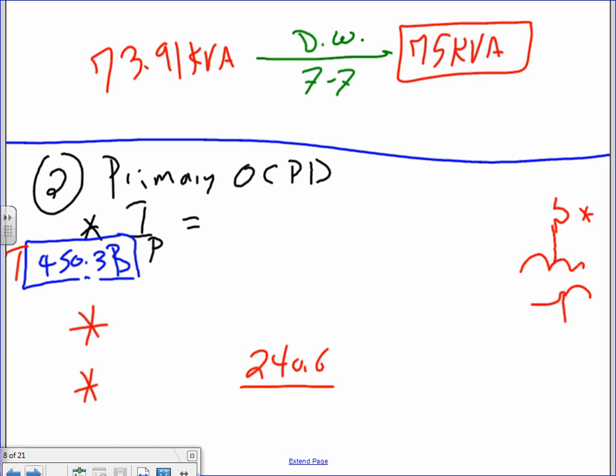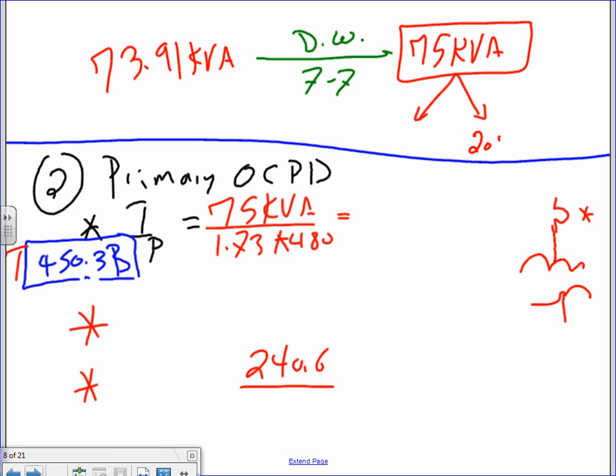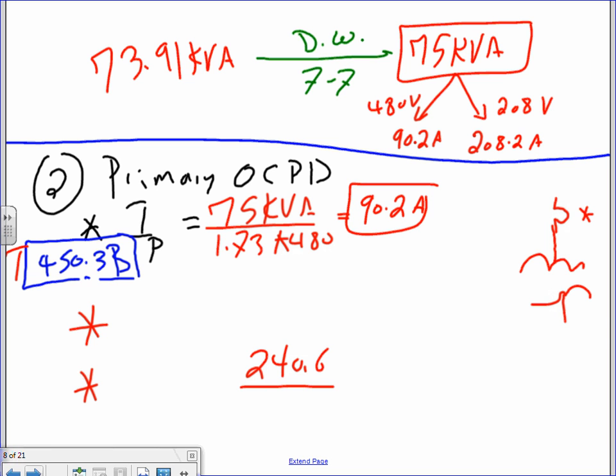Okay, now after this, Adam, straightforward. We found the size, 75 kVA, drop it in Revit, and then I need somebody to help me with the calculation. kVA, divide this by 1.73 times 480. And by the way, this is also coming from the sheet. Derek, why don't you give me this from the sheet right away? The full load amp for the two of them, because it's already there. 75 kVA, at 208 volt, and at 480 volt, 90.2 amps. That's directly from the sheet, guys. When you do the math here, you should come up with 90.2 amps. Or you can get it directly from the sheet. You can see that the sheet will give you the same number. It's already done for you. Okay.